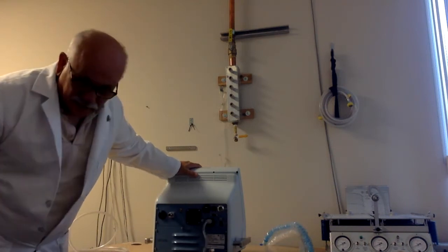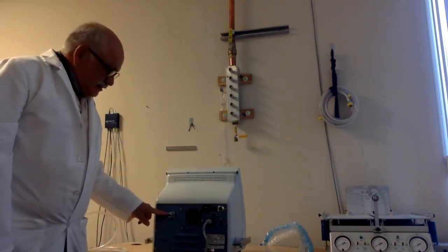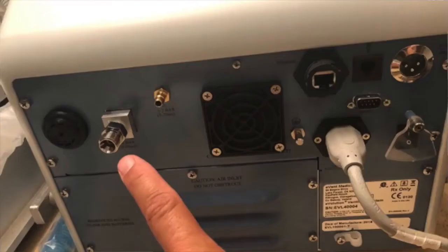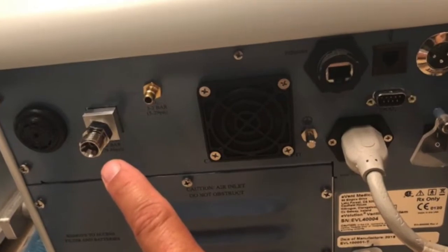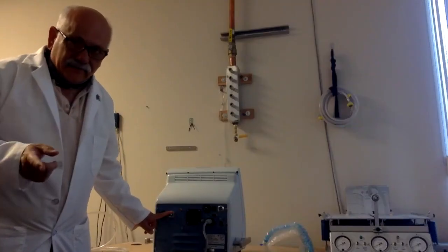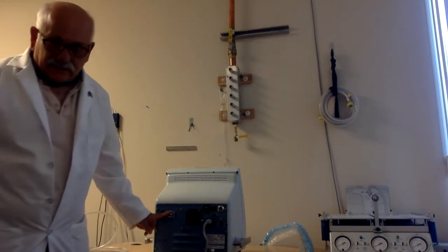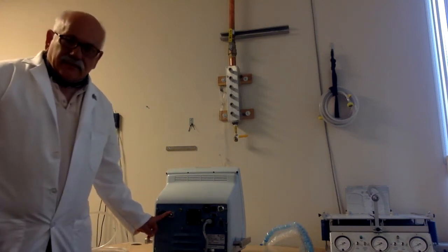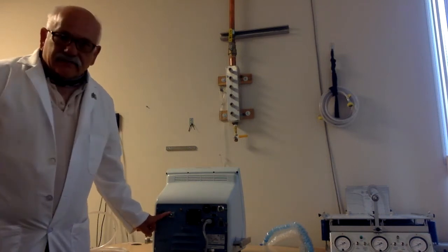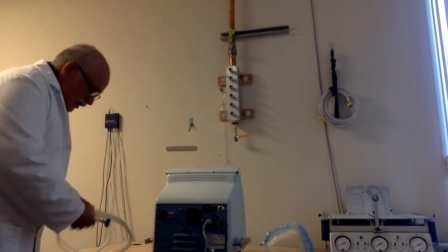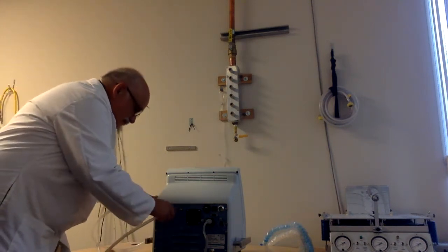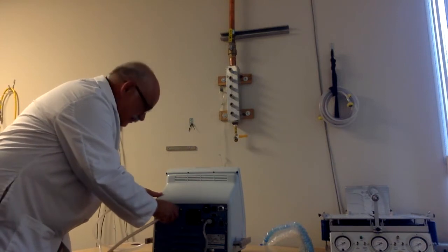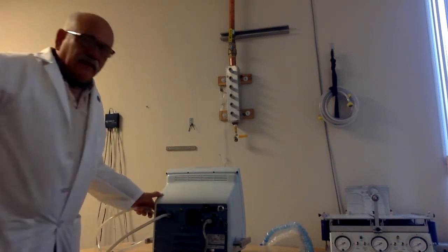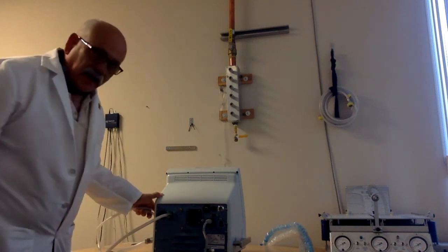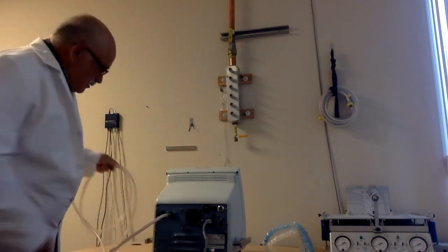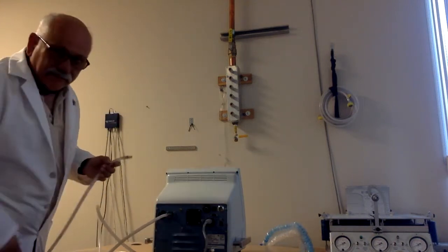Now, one of the clues here as to the type of ventilator we're talking about is that it only has one manifold for gas. Generally speaking, you'll see two manifolds, one for oxygen and one for air, in an ICU ventilator. But some ICU ventilators have emerged that use turbines or blowers, and in those cases, they only require oxygen. So I'm going to attach our oxygen hose. We'll run the ventilator on 21%, but just to show you how it works, I'm going to go ahead and attach the oxygen hose. You can see the green color code, and I'm going to reach up above and plug it in just a minute.